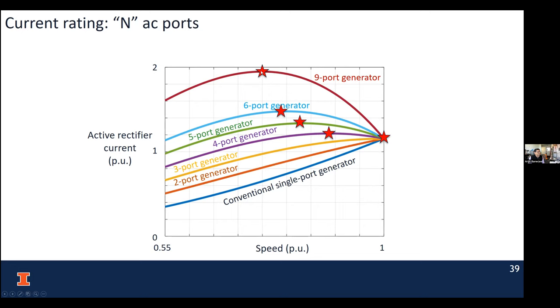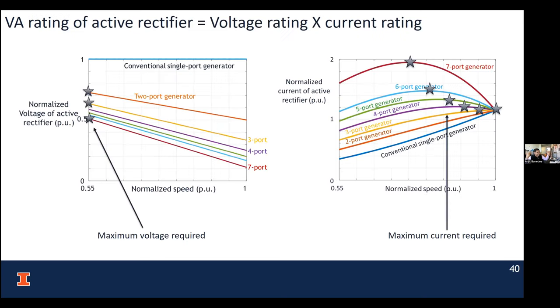You can see the peak of the current changes where it happens, and gradually it starts increasing. So if you have a nine port generator, the current rating requirement is much higher, although you've reduced the voltage rating requirement. So if we want to optimize the VA rating of this new architecture, particularly the active rectifier side, we have the voltage rating, the current rating, and our degree of freedom is the number of ports.